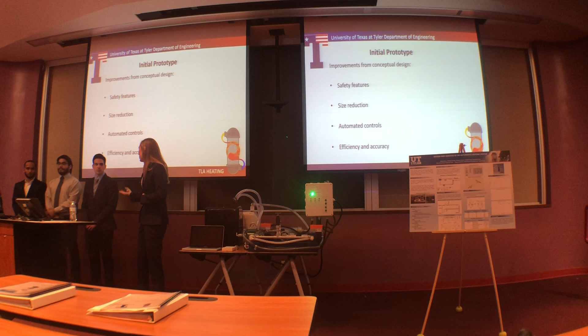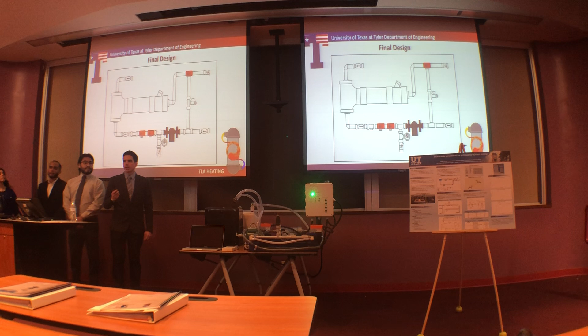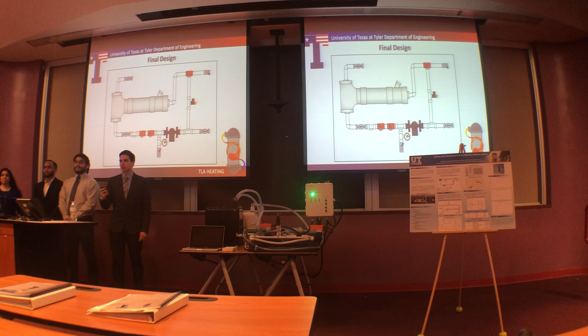Our final design is composed of a pump that provides the flow for the system, and 3 actuator valves that are in charge of deviating the flow to the heater and chiller, depending on the situation and what temperature we want to reach. We have the mixing chamber that provides enough space for the hot and cold fluid to mix in order to obtain a stable, controlled temperature. We also have safety features: 3 check valves to prevent backflow, 2 ball valves to avoid any leakage when disconnecting the system, and a pressure relief valve so that if pressure builds up, we can release it without damaging the system.